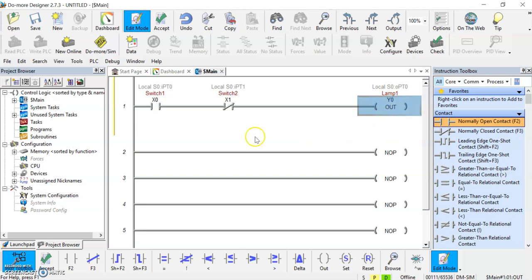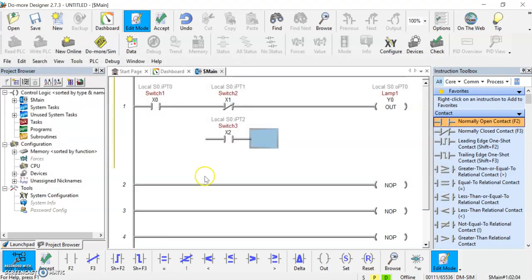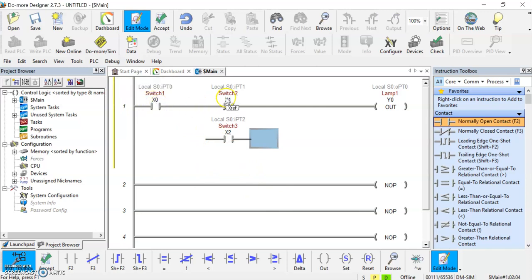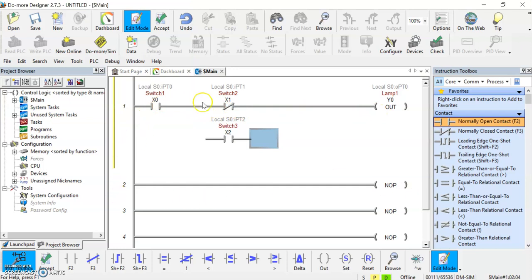What if we want an OR statement? Well, go right below switch 2 here and you notice that a blue box opens up here. Let's hit another F2 there to get us a normally open switch, and we're going to call that switch 3, enter, and we'll assign that as an X2, and there we go. So if we take a look at all the switches, they're all different address assignments: X0, X1, X2, Y0. But you can see this isn't attached to anything, so the instructions that the PLC is going to read through, it follows this gray line through until it gets to there and then it'll go to the next rung. But this isn't attached, it's not even attached over to here.